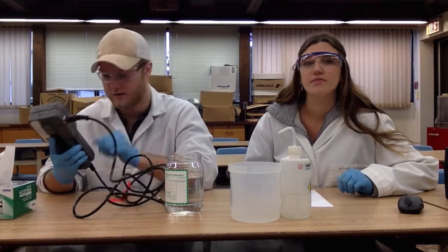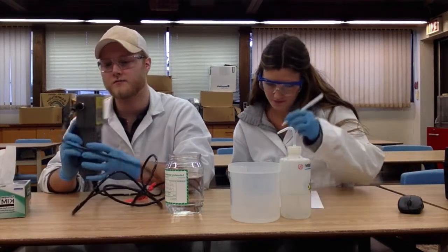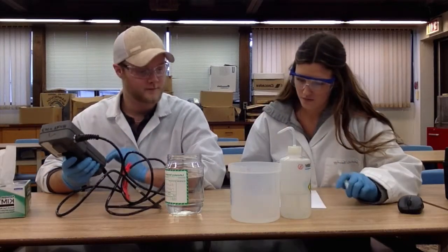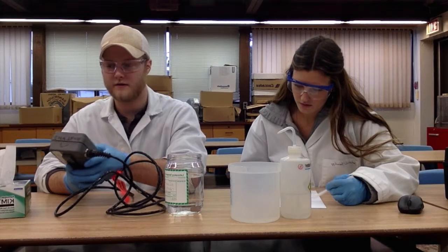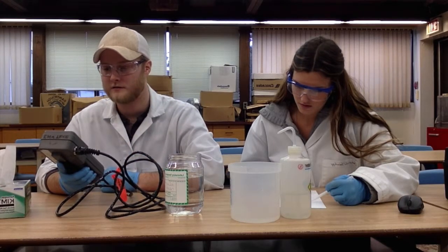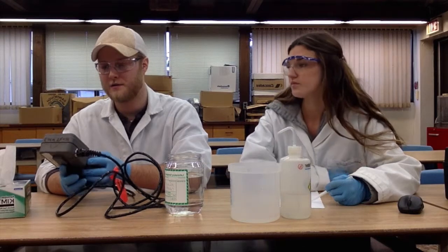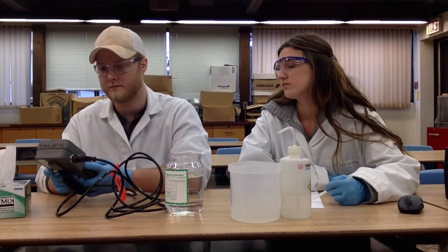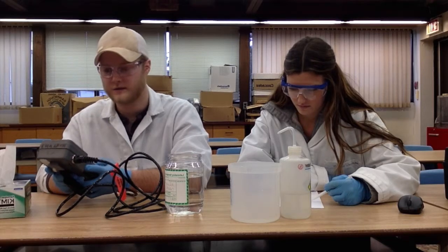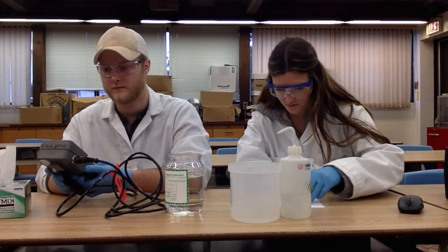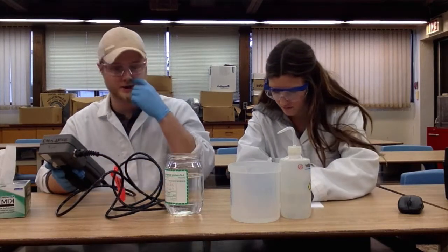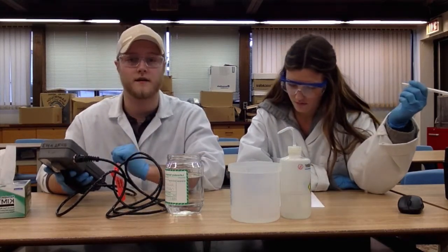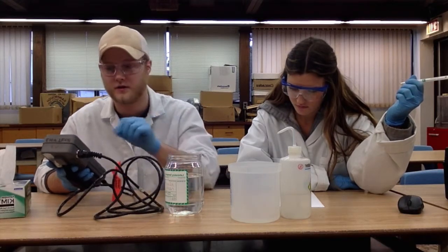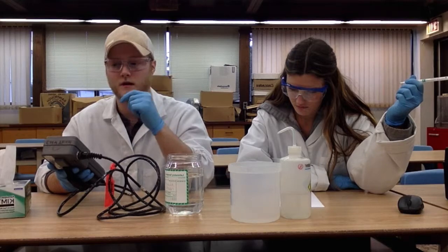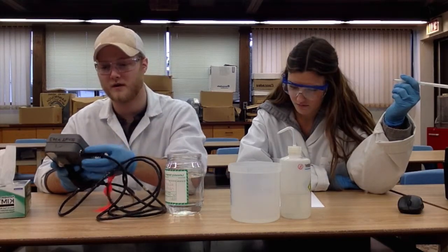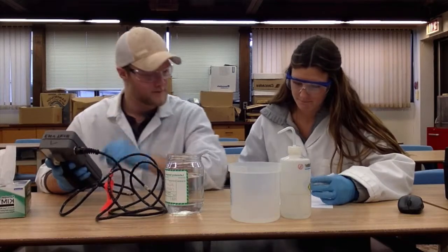Alright, so now we're doing conductivity. First they're going to check that all the cords are on right, and check the unit, make sure nothing's broken, functioning properly. And then I'm going to go ahead and turn it on. So we're going to ensure it's in microsiemens. And then we're going to change the mode to make sure that we have proper compensation for the temperature, because the conductivity will change with temperature.